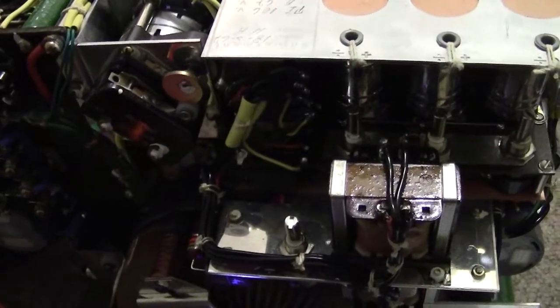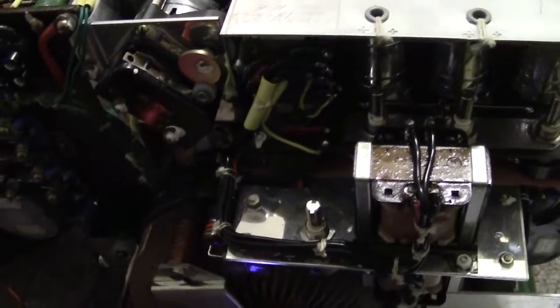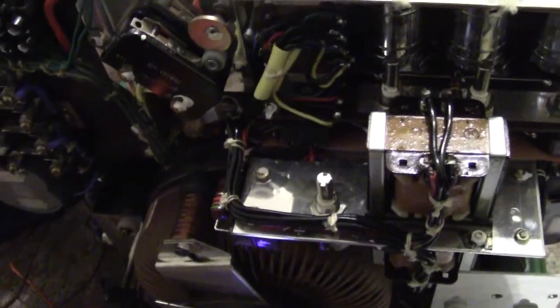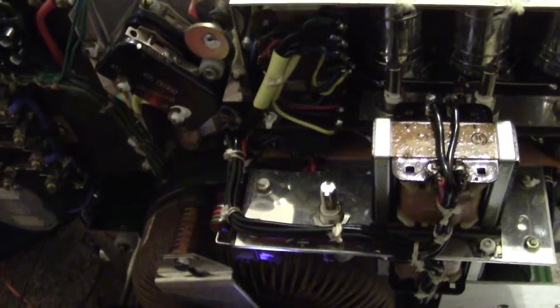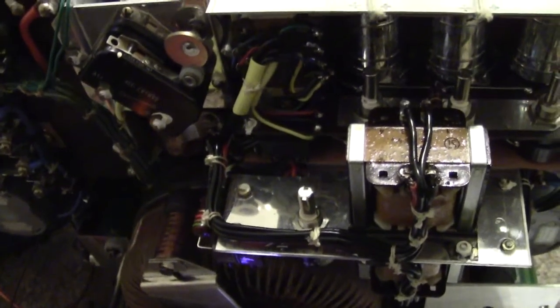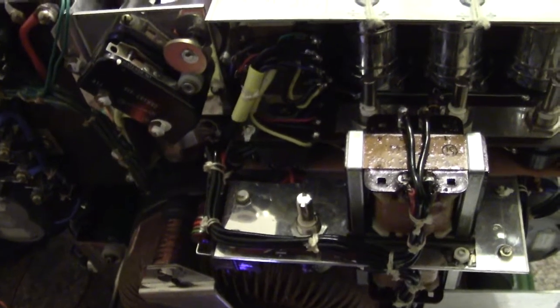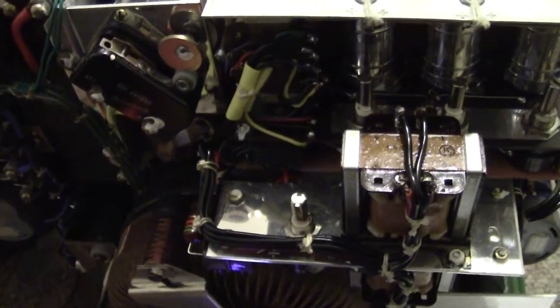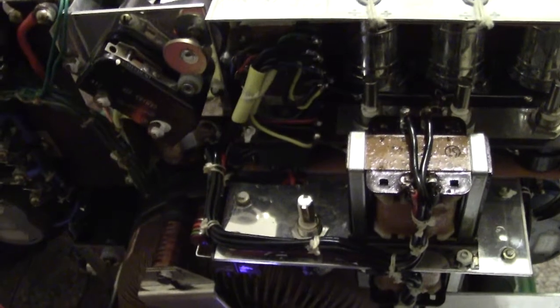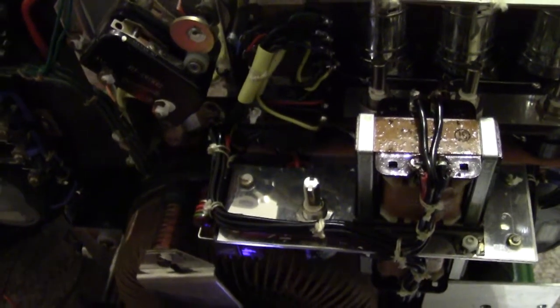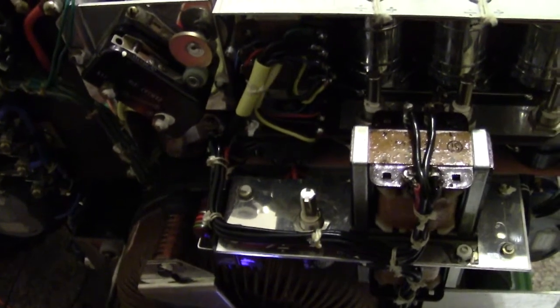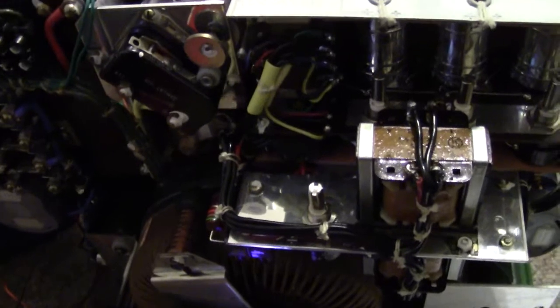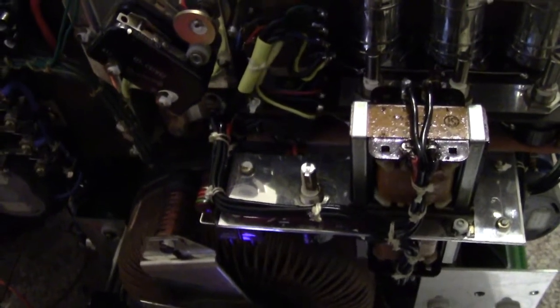So to make an X-ray give out 150 kV at 10 milliamps, if you wanted to change it to 150 kV at 5 milliamps, you can't just change the input voltage, and you can't just add a ballast, because that would take away the current allowed to be drawn by the transformer, since X-ray transformers aren't current limited.